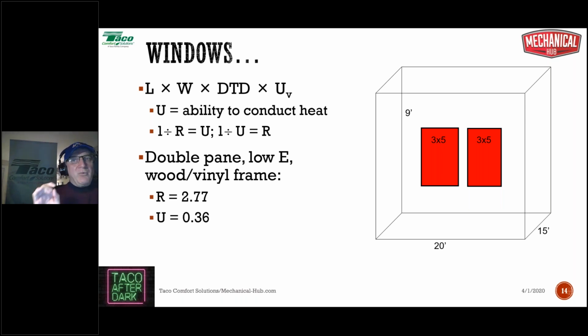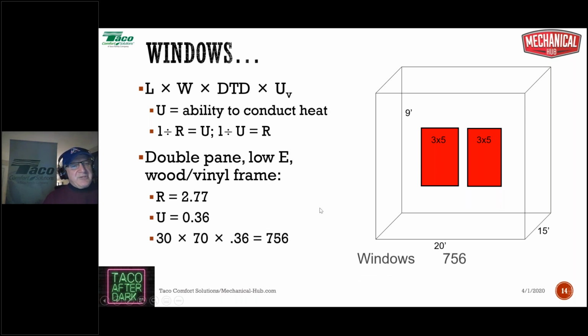Remember, gang, we're not flying this thing to the moon, it's a house. We're trying to replace heat, we don't have to get too crazy about this. Call it 30 square feet and we're going to call it good. It's a house, it's not a rocket ship. So in this case, what we can do is 30 square feet times 70 degree design temperature difference times a 0.36 U value. That's going to give me a BTU load for my windows of 756. 756 BTUs through the windows.